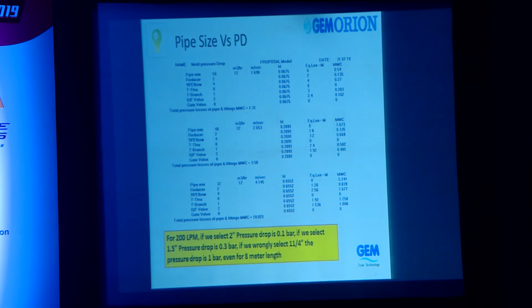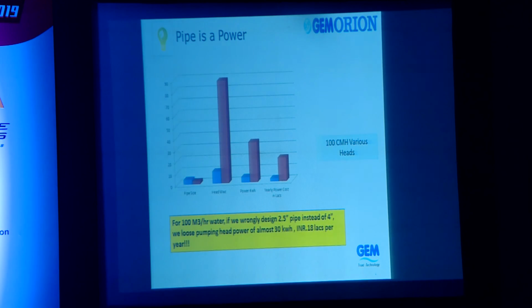So this gives a typical software output of what is the power or pressure drop when you wrongly select a pipe. See, I have shown as an example for a 200 LPM flow. If we select a 2-inch pipe, the pressure drop for 8-meter length is 0.1 bar. But if we select 1.5 by mistake, instead of 2-inch, it is 0.3. And if you select 1 and 1/4, the pressure drop is 1 bar, even at 8-meter length. So that is figuratively shown here. The difference in pipe size is only so much, whereas the head is abnormally high. The power is also very high, as well as the yearly running cost.